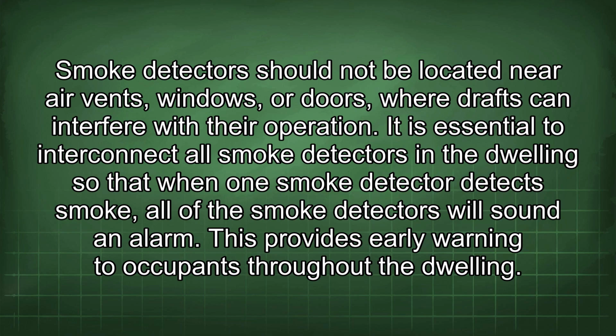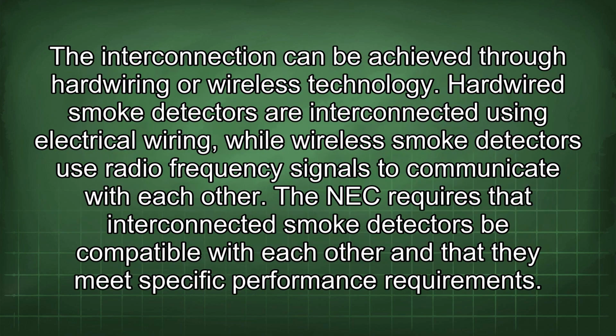It is essential to interconnect all smoke detectors in the dwelling so that when one smoke detector detects smoke, all of the smoke detectors will sound an alarm. This provides early warning to occupants throughout the dwelling. The interconnection can be achieved through hardwiring or wireless technology. Hardwired smoke detectors are interconnected using electrical wiring, while wireless smoke detectors use radio frequency signals to communicate with each other. The NEC requires that interconnected smoke detectors be compatible with each other and that they meet specific performance requirements.